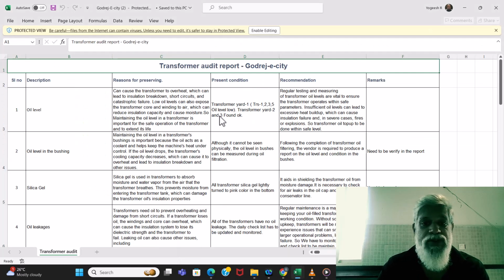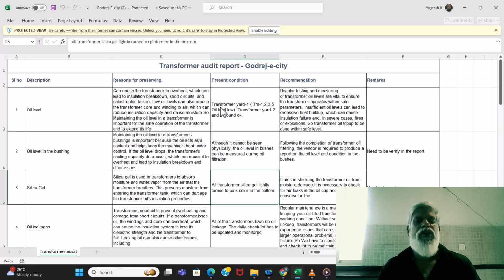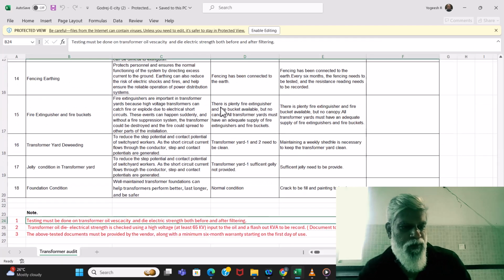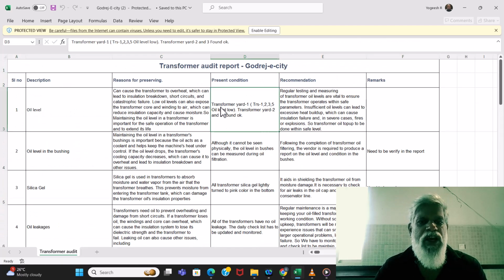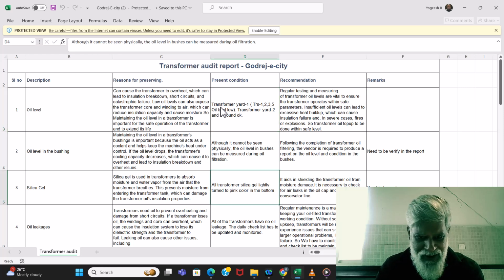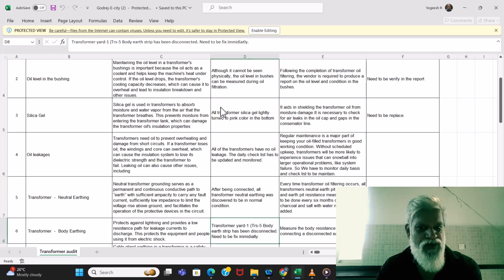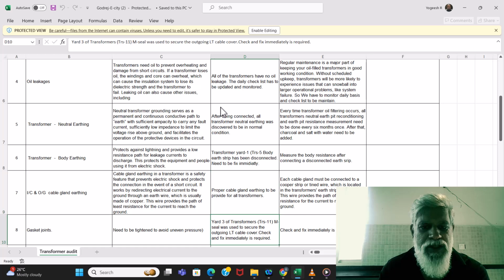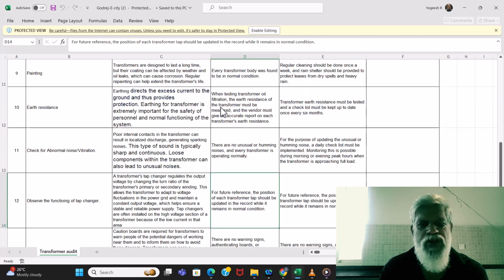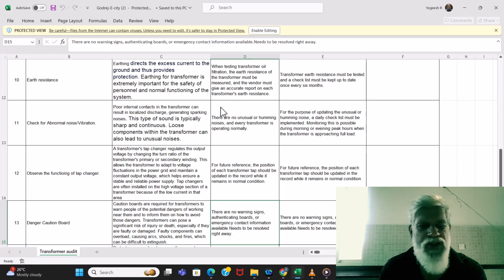And once the service was carried forward, Paradigm again came back to the site to check if all the audit points are closed or not. And amongst 18 audit points, we have an anomaly with 2 of those. One is transformer yard 1, 2, 3, and 5. Oil level is still not at the top, but it's okay. It's a little low. So that's something that internal team will take care of. It needs about 5 to 6 liters of oil in each of these that can be topped up from internal team. And the second anomaly which we found was in transformer yard 1, one of the body earth strip was disconnected. So that's something that we will fix internally. And apart from this, the majority of these are cosmetics like cleanliness of HDR and certain signage boards.